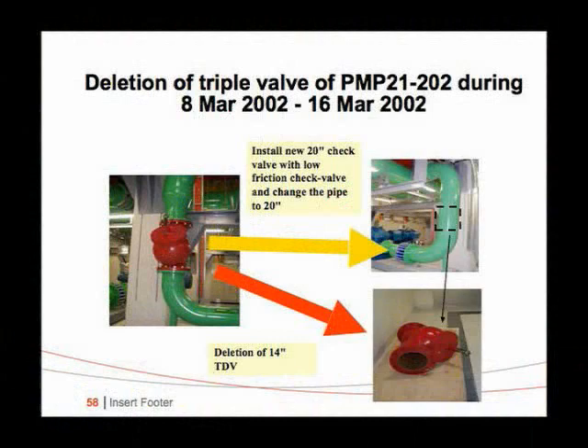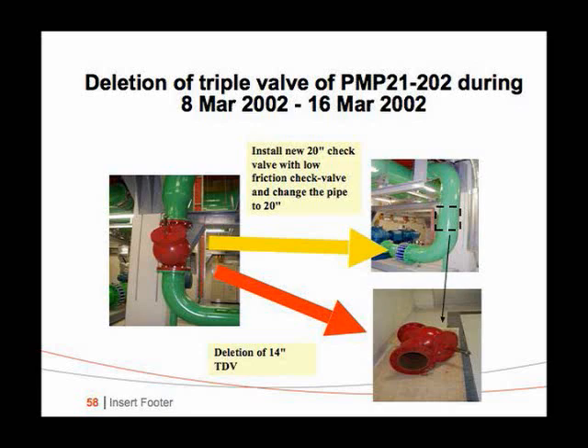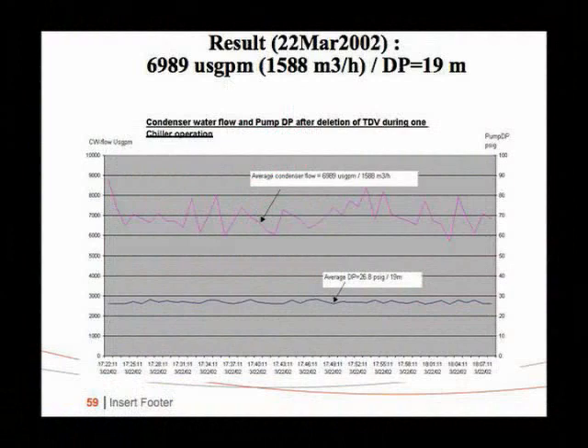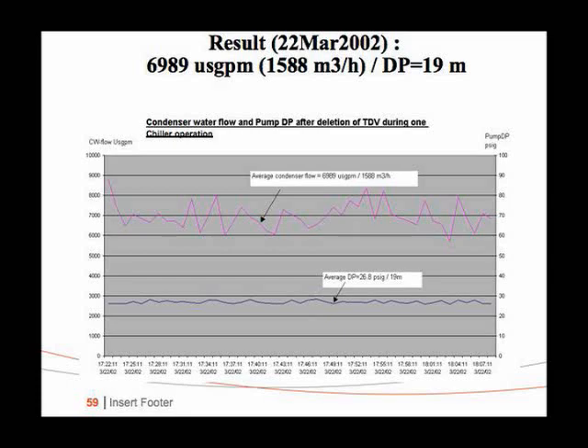So here is a 20-inch pipe. This vendor only makes 14-inch valves, so they neck it down from 20 to 14, which is a tremendous restriction. It's 6 months old. We take it and put it on the floor and put a bypass section, which increases the flow rate. This is the flow rate this time, from here to here. And we are getting a tremendous increase in flow rate for a very slight increase in pump kilowatt. Won't bore you with the details, but we can remove 350 kilowatt just by tuning.